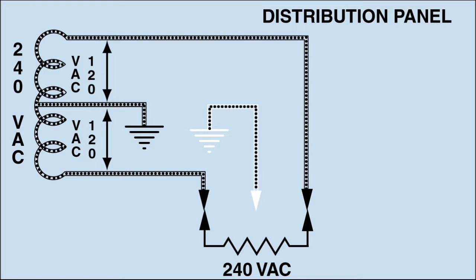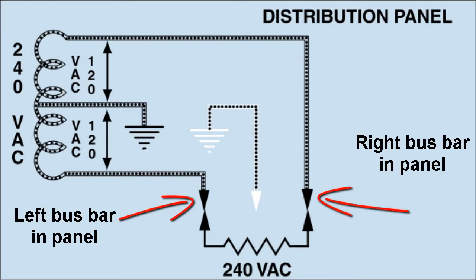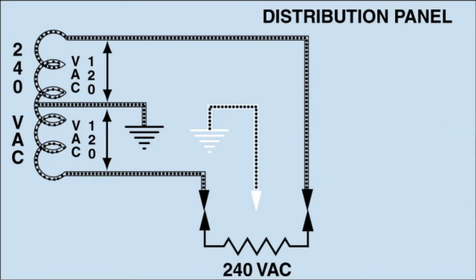A 240-volt load has no connection to neutral and does not need one. Current flow is from bus to bus, which is the same as saying from one end of the secondary to the other.